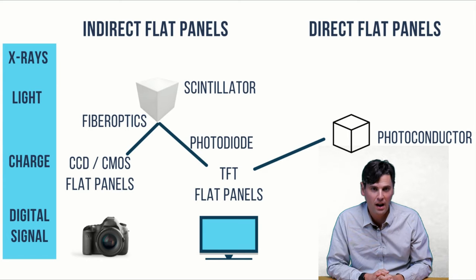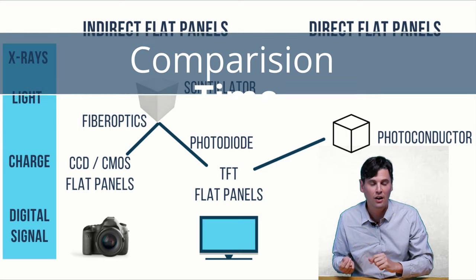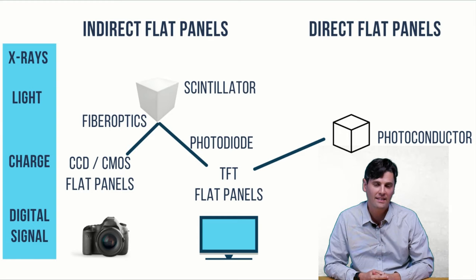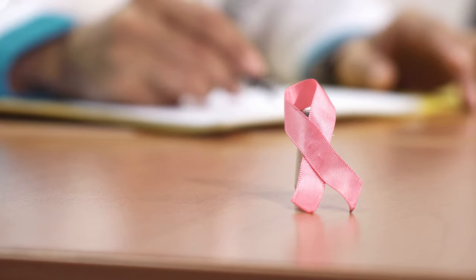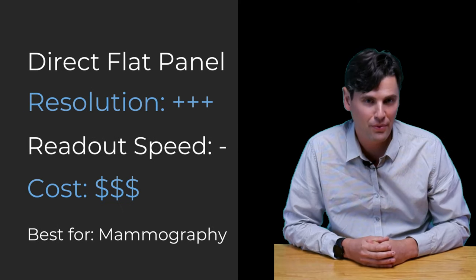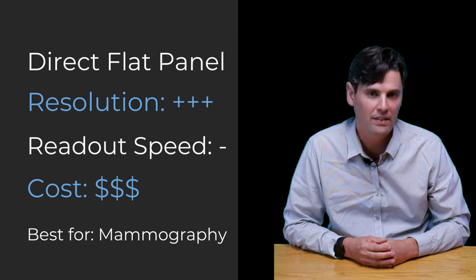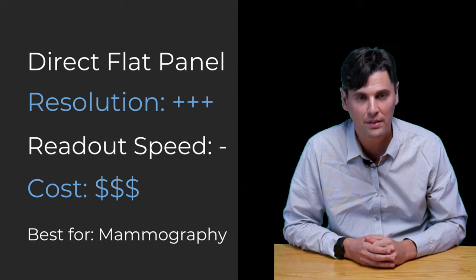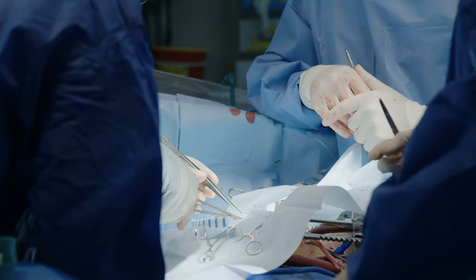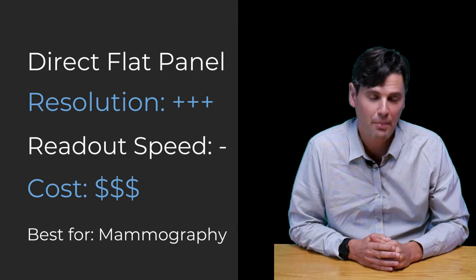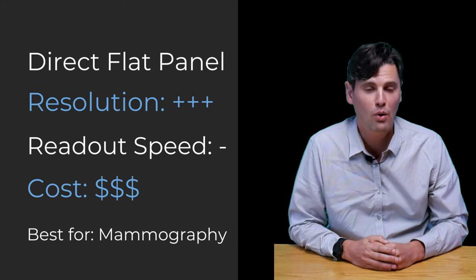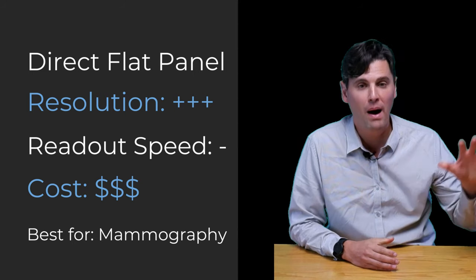Now for the comparison of all three options: CCD, TFT arrays for indirect, and direct flat panels. If your task is mammography — where spatial resolution is of utmost importance to see microcalcifications — you'll want the direct flat panel for the highest spatial resolution. These are the most expensive systems and readout is not as quick, so they are not ideal for angiography procedures. Direct flat panels are also better at detecting lower-energy x-rays, making them less suitable for large patient imaging at higher energies.